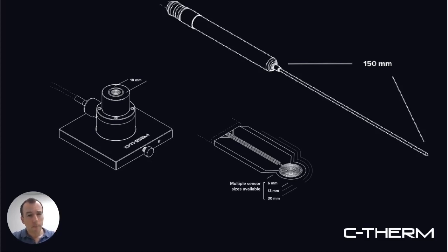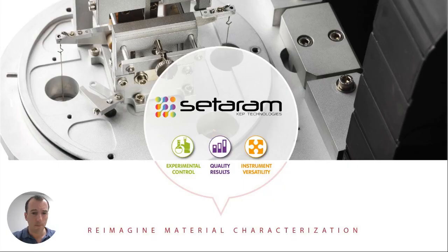And then to the left is the MTPS. This is the single-sided sensor. This is the easiest to operate. It has an active area of about 18 millimeters in diameter. That's the area that has to be fully covered by the sample, but it is as close as you can get to one button push for thermal conductivity characterization. Very much an automated analysis of the sample result. It makes it really easy as a user to do this. We have high school students that come through and operate this equipment with very successful results. So it just speaks to the simplicity of use.